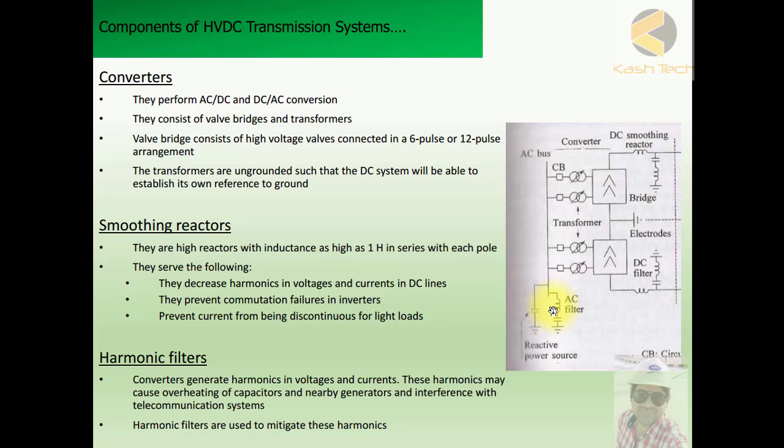Next we have harmonic filters. Converters generate harmonics in voltages and currents, which may cause overheating of capacitors and nearby generators, and interference with telecommunication systems. Harmonic filters are used to mitigate these harmonics. Since harmonics are multiples of the fundamental frequency, the filters are used to eliminate these harmonic components and make the system smooth.